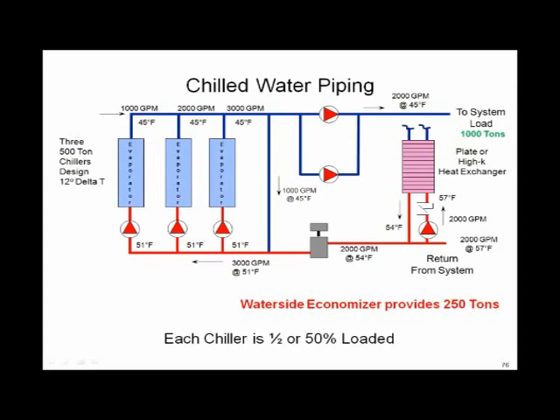So let's go to the common pipe and see what happens at the chiller plant. So now I got 2,000 GPM of 54-degree water coming back. And as you can see, it's mixing with 1,000 GPM of 45-degree chilled water at the common pipe to give me 3,000 GPM of 51-degree water going back to my chillers. So each chiller is seeing 1,000 GPM at 51 supplying 45, 6-degree delta T. So what do you see? The design is 12. Each chiller is doing a 6-degree delta T. Each chiller is 50% loaded. Everybody's happy. It would not be unusual to run 3 chillers in this situation because most machines would be more efficient around 50% versus running at some higher number. You've got to make that decision based on your chiller load profiles.